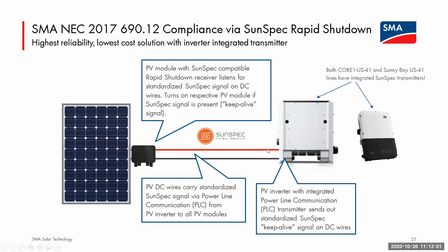So under normal operation, that transmitter is telling these receivers everything's fine through a keep alive signal. If that signal is lost, meaning when the AC disconnect or the power is lost to the building or the AC disconnect is turned off, AKA a firefighter or first responder comes to the building and shuts off the system, that signal is lost from the DC lines, and all of these devices go into a rapid shutdown mode.